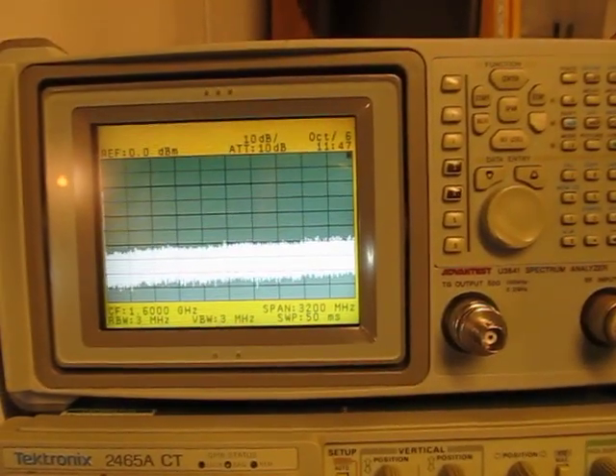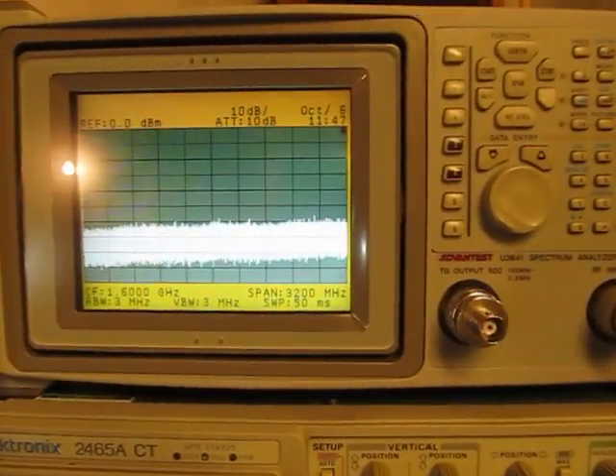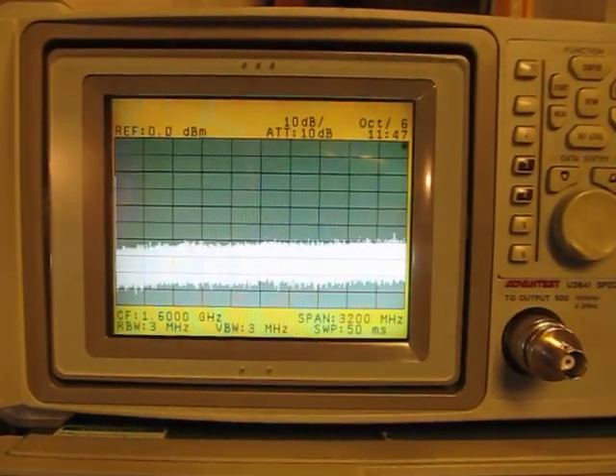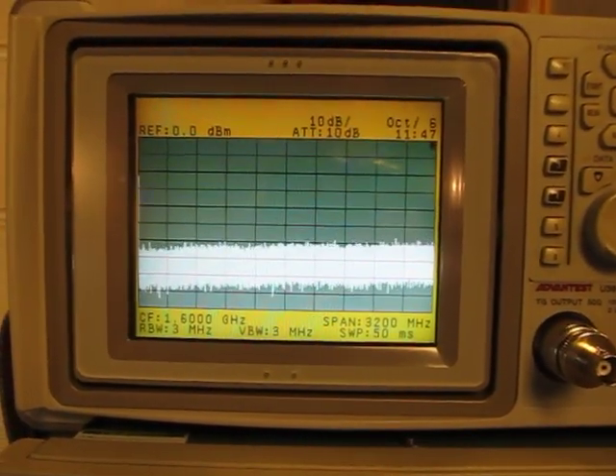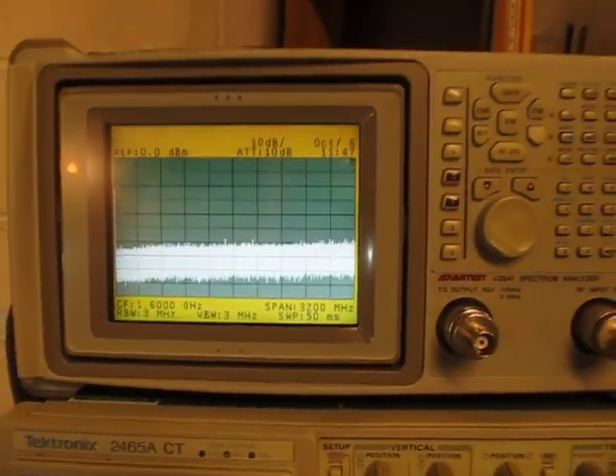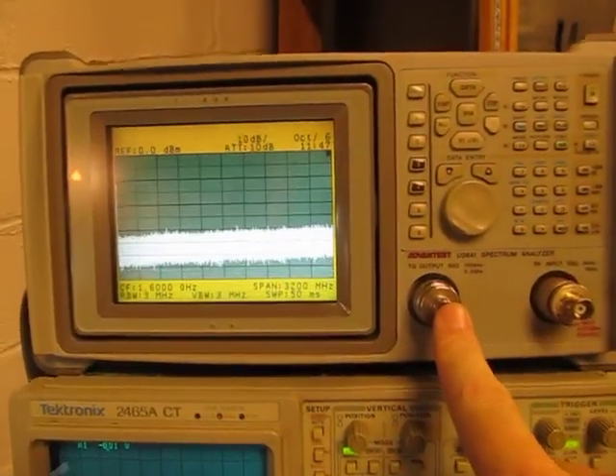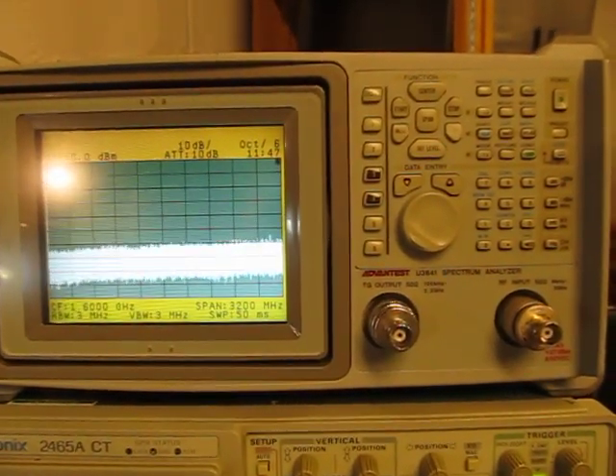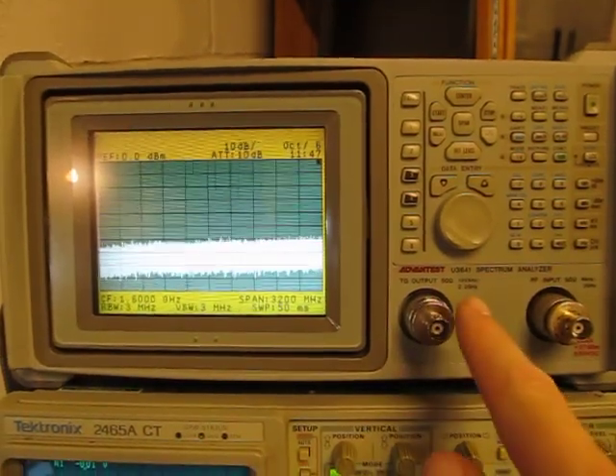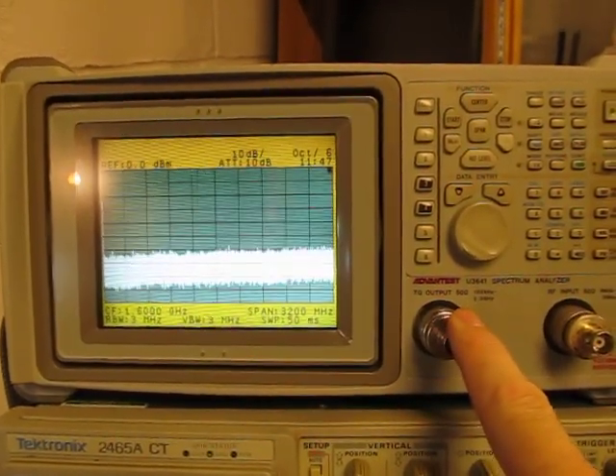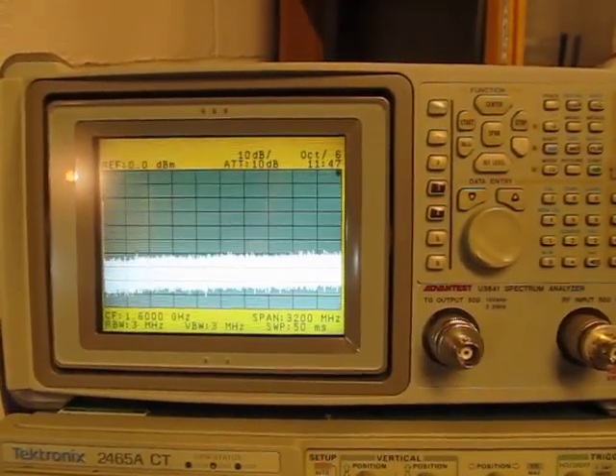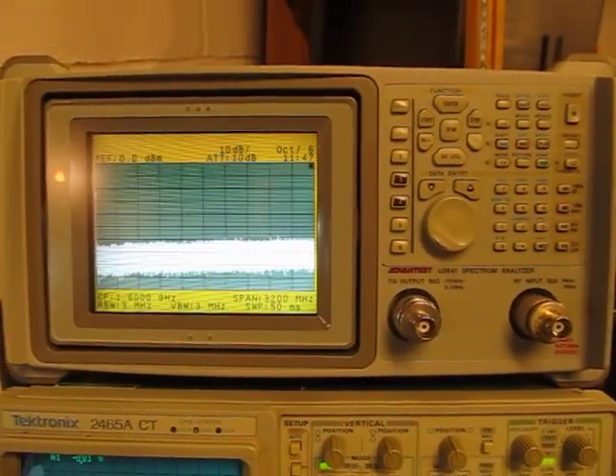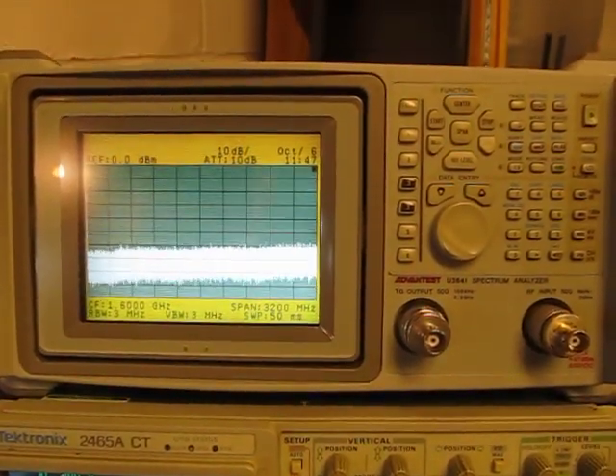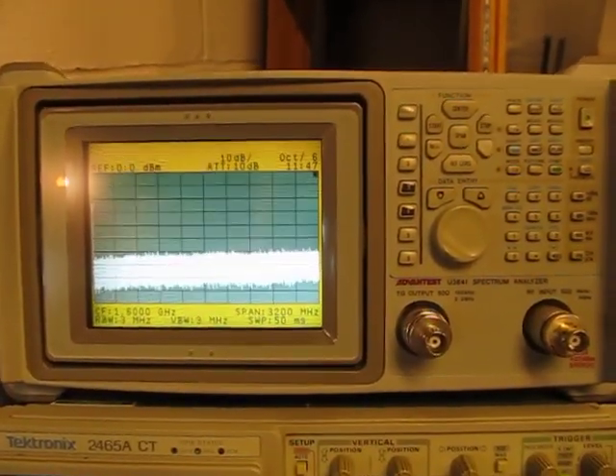Okay, in this video we're going to talk about the basics of a tracking generator, what it is, and a quick example of how you use it. A tracking generator is typically an accessory, an optional feature in many spectrum analyzers, and it's used to help you measure the frequency response of components like filters.